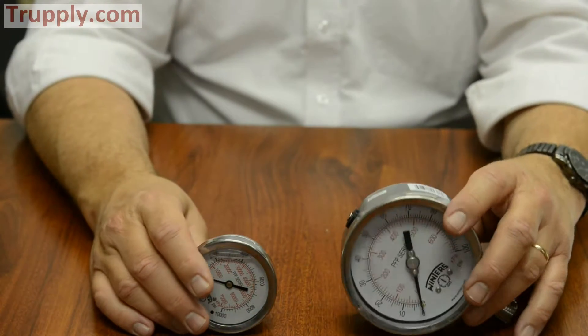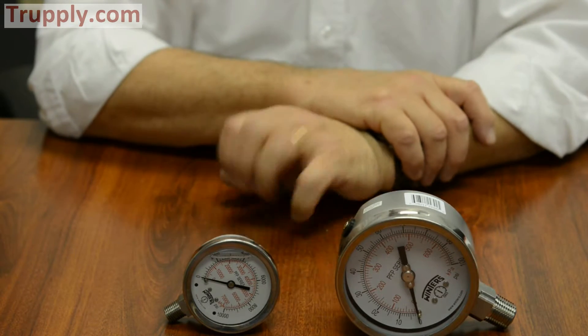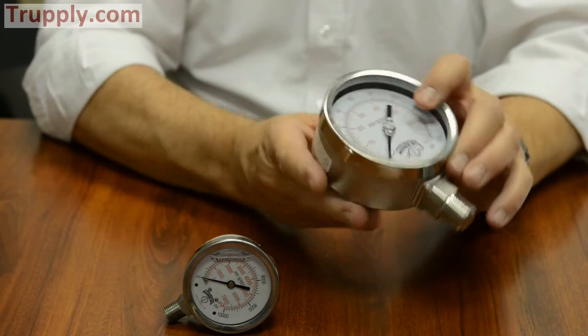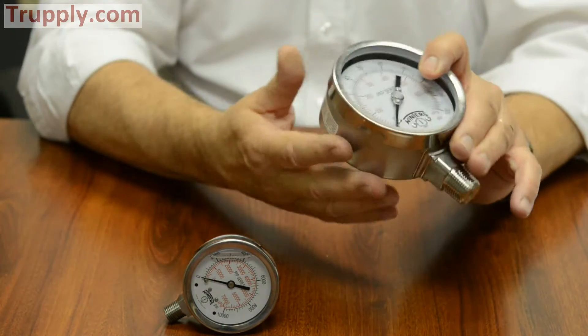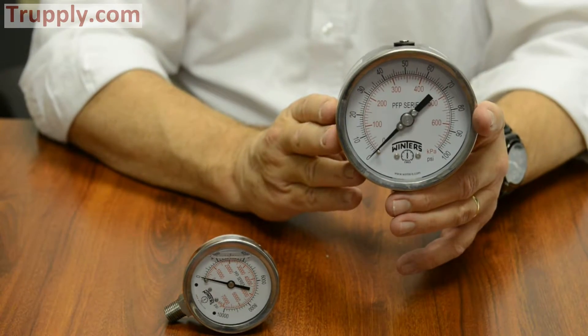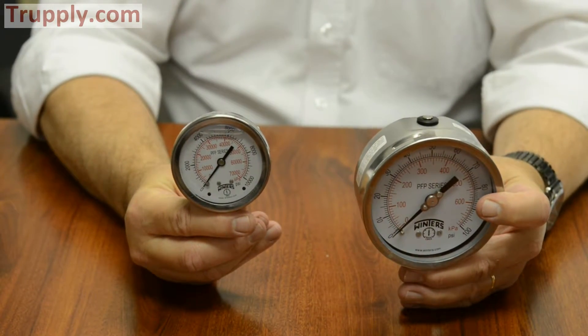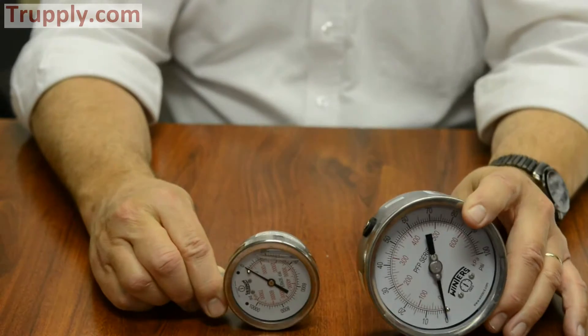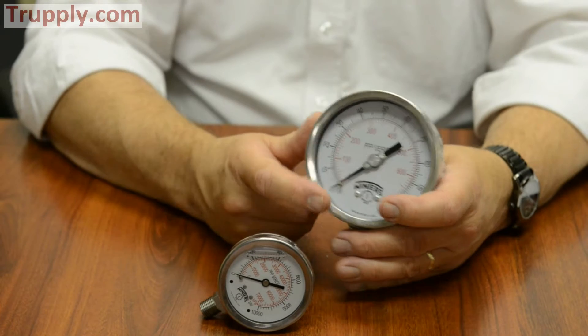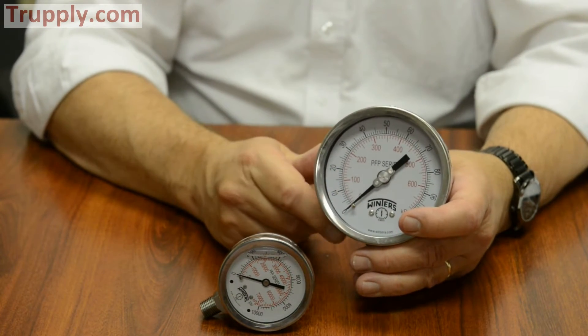These gauges are made for heavy-duty industrial applications. They come liquid-filled standard and have full-size movements. This is a beefy gauge with full-size Bourdon tubes. The accuracy of the 4-inch is 1% full-scale and the accuracy of the 2.5-inch is 1.5% full-scale. They come standard with an acrylic lens, but are also available in laminated safety glass as well as other materials.